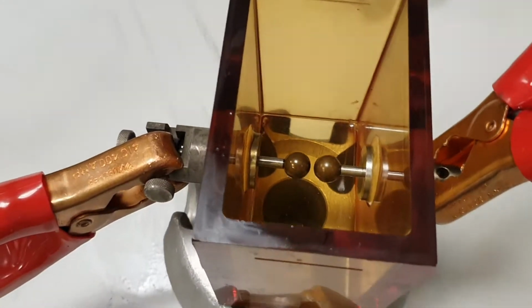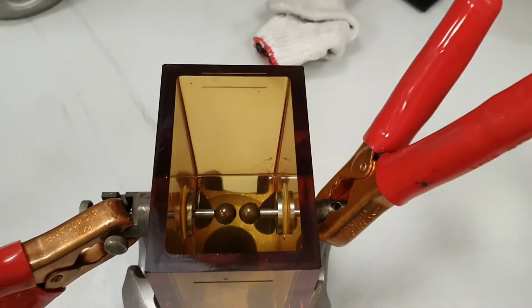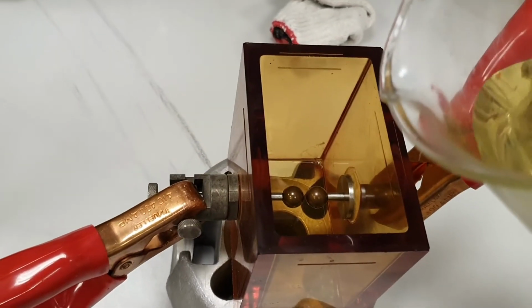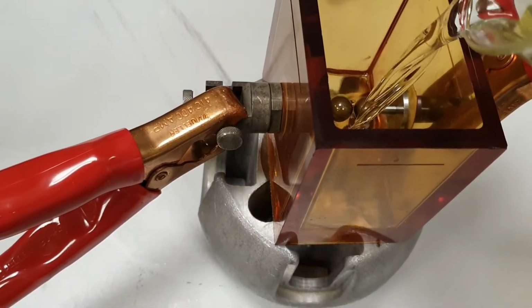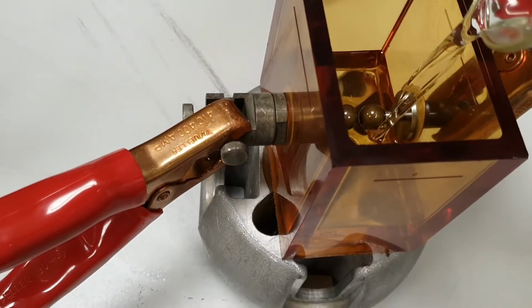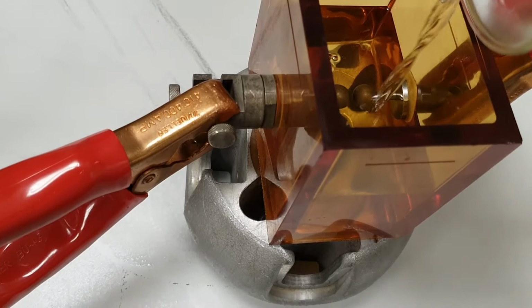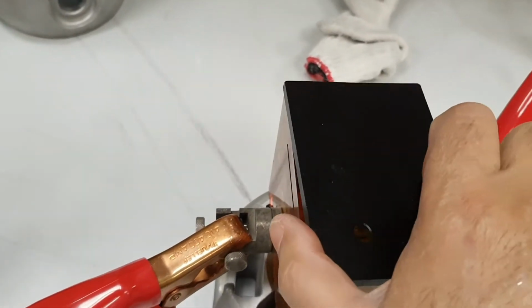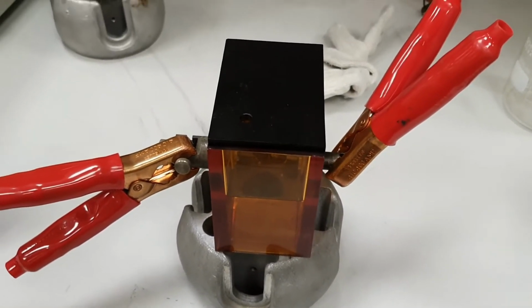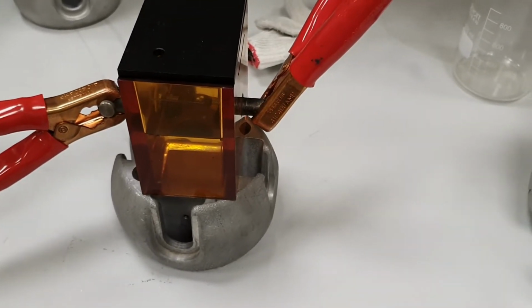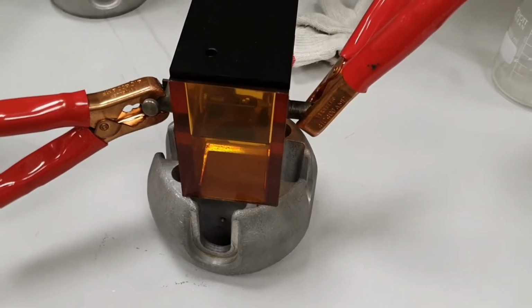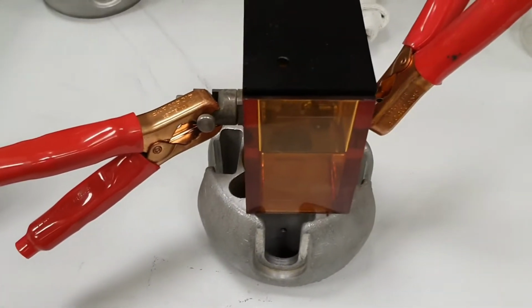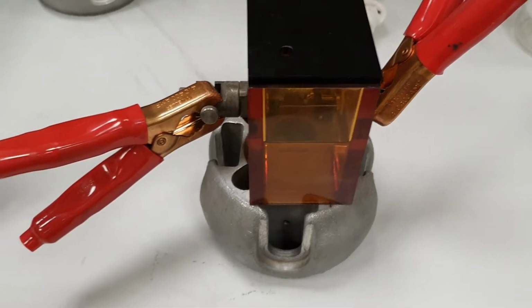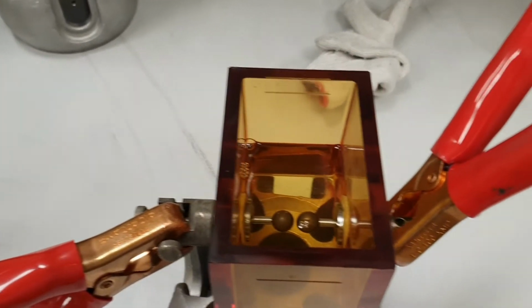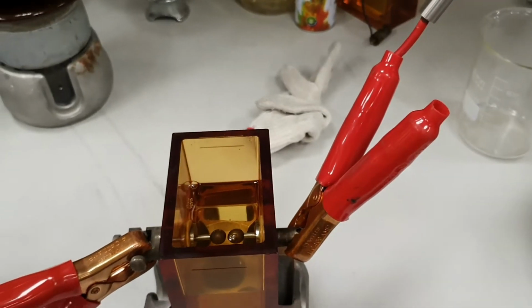So we have transformer oil here. We'll pour this oil inside this one. Again, you should make sure that both the electrodes are fully dipped in the oil. Again, close this lid here. Okay, so repeat the setup with the oil, previously without oil, just for the air, then again filled with oil, and then you will have tan delta for this transformer oil.